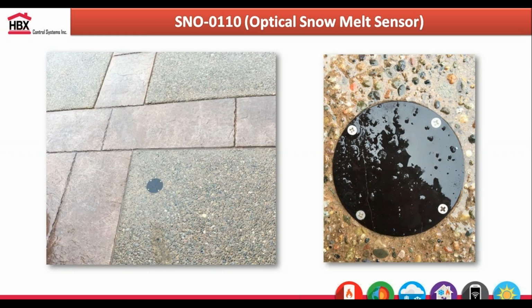Say you have teenagers and you only want it to come on after the snow is about 3 or 4 inches, or you have a vacation home that you only go to maybe once or twice a month in those winter months, you really don't want your snow melt system running all the time. That really gives us flexibility compared to other sensors, which are really just a moisture sensor, and once a drop of snow hits it, it automatically turns on, triggering 8-hour snow melt mode when maybe just some snow has fallen onto that sensor.